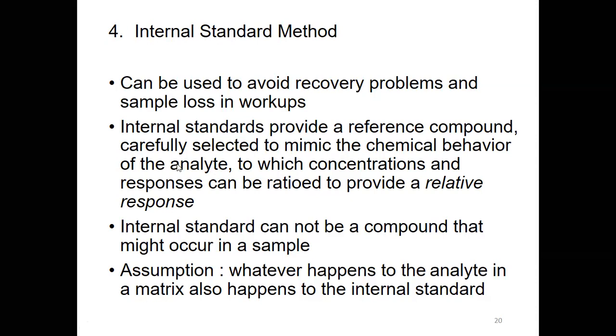The internal standard is a reference compound that should mimic the chemical behavior of the analyte, like lithium for sodium. When we measure the sodium concentration, we add lithium as an internal standard. So lithium mimics the chemical behavior of sodium. And by taking the concentration ratio of the lithium and the sodium, we should be able to get a relative response.